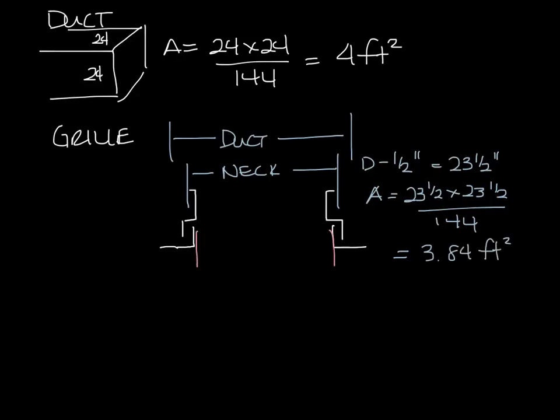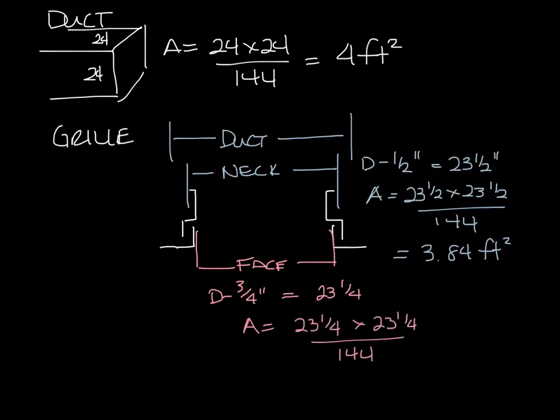But the face of the grill is a little smaller than that. It's three quarter inch smaller than the 24 by 24 dimension. So now we have 24 minus three quarters is 23 and a quarter. And so that area is 23 and a quarter times 23 and a quarter divided by 144 is 3.75 square feet.